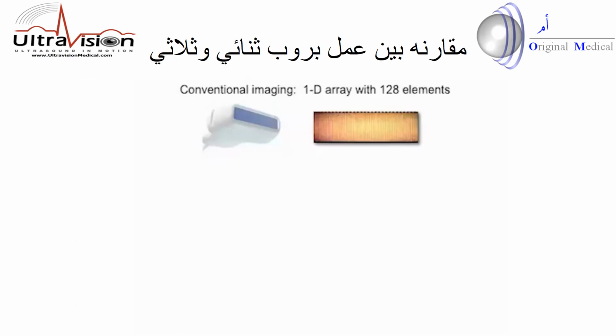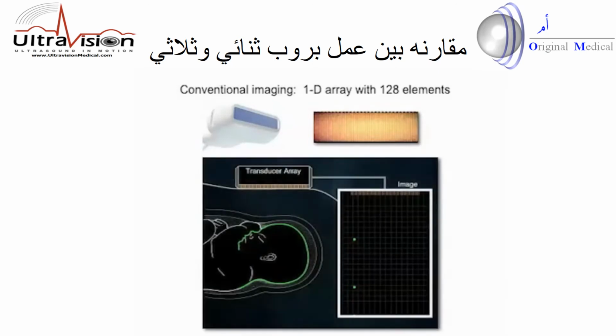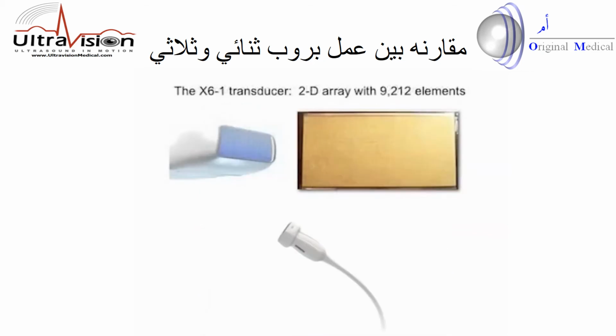A conventional transducer has a number of elements aligned in a row, and these elements are excited in groups and echoes detected one at a time to form the lines of an image, perhaps 100 or 200 lines that make up a B-mode image. The plane of this image is defined by the direction that the transducer is pointing in, and if we want to change that plane, we have to move the transducer either with our hand or with a motor in some transducer probes. The X6-1 is quite different.